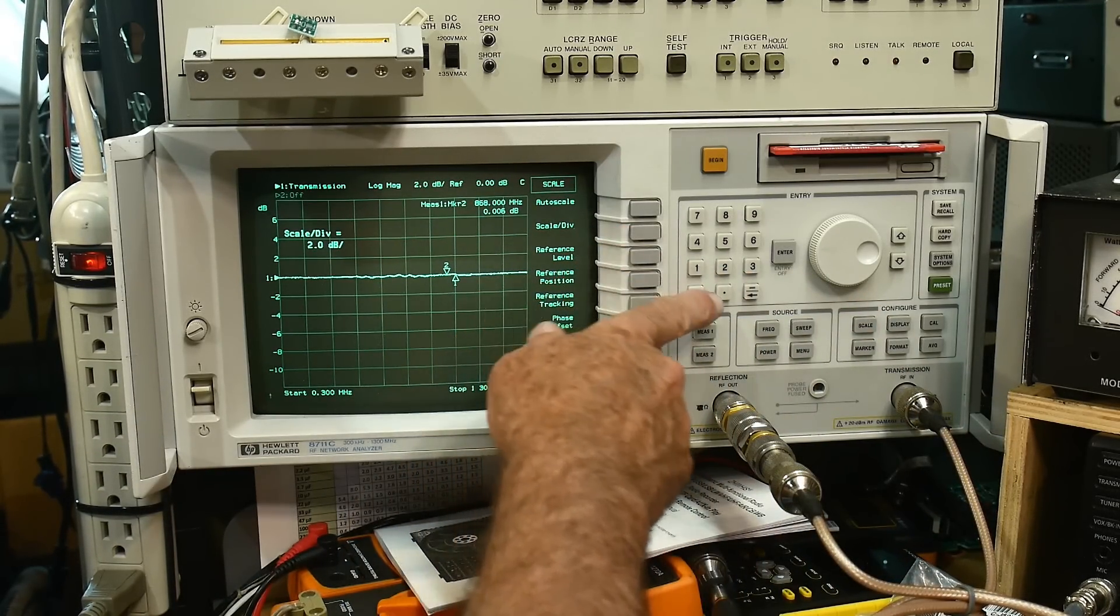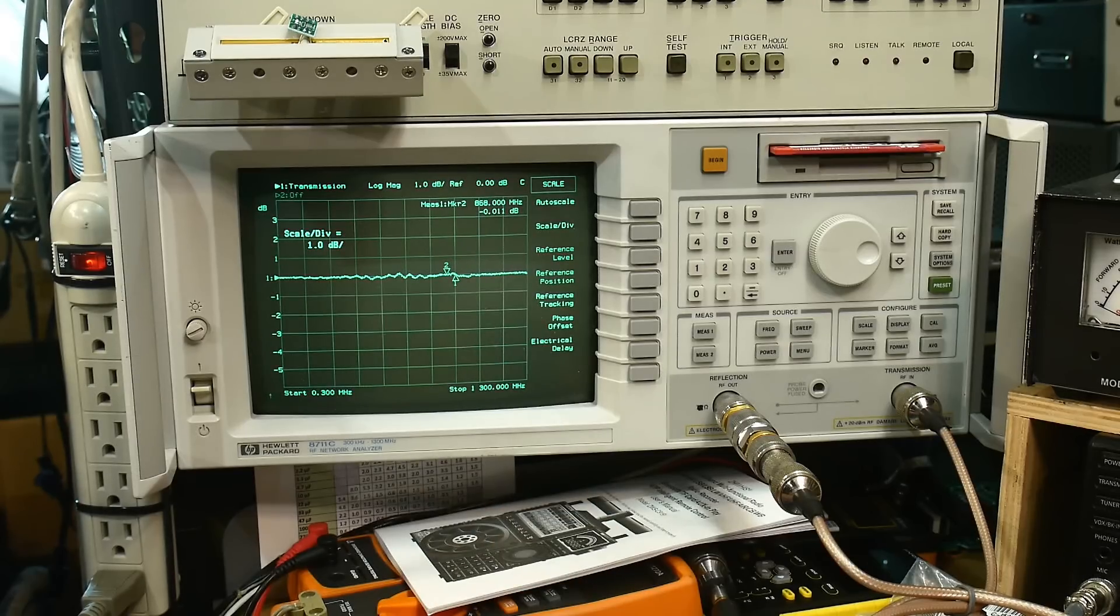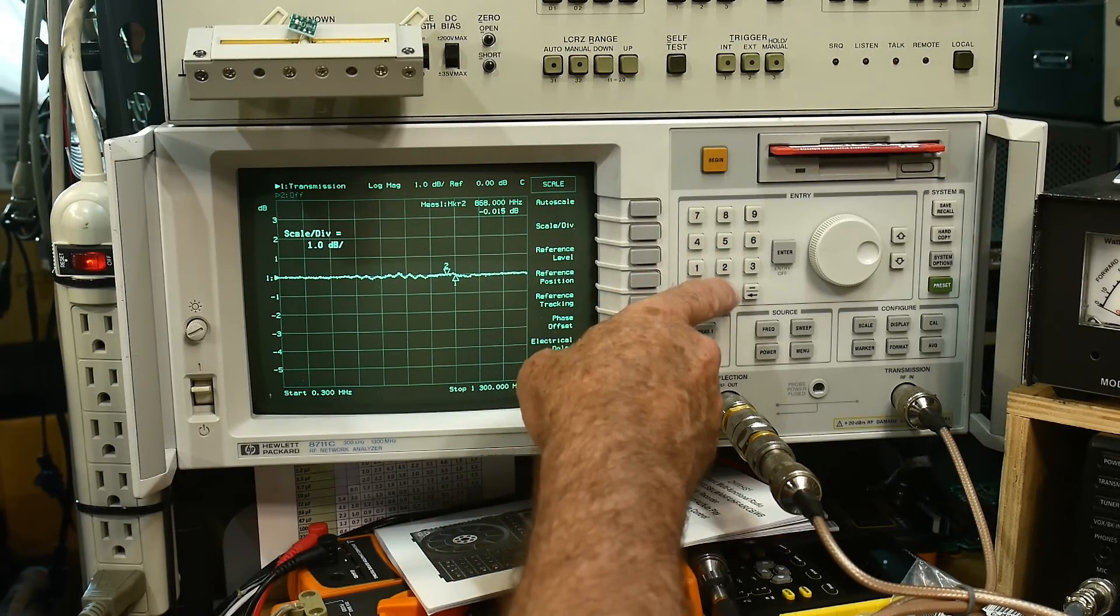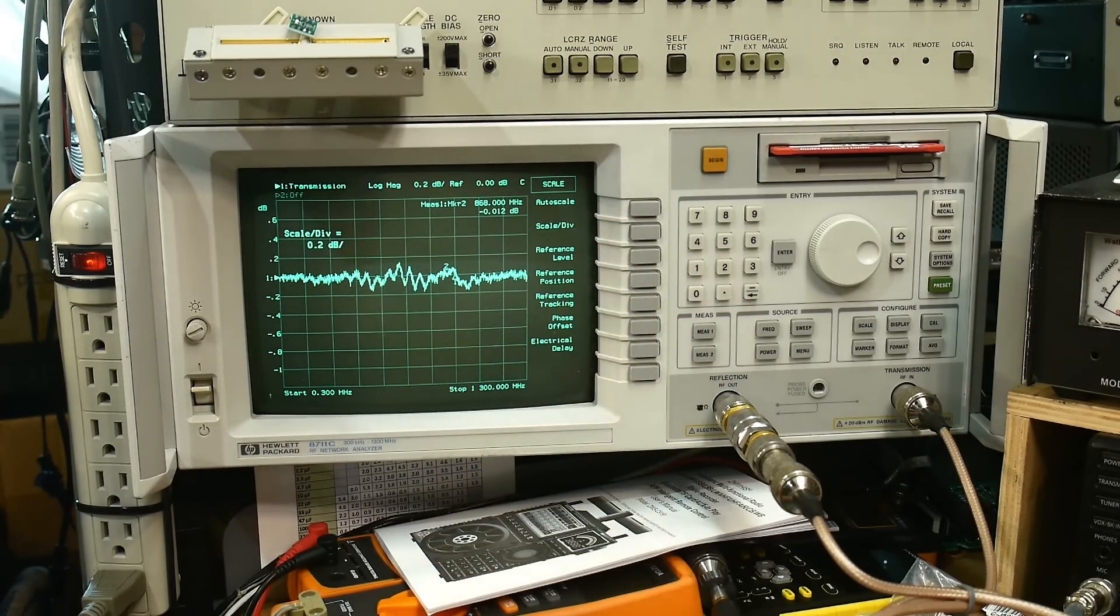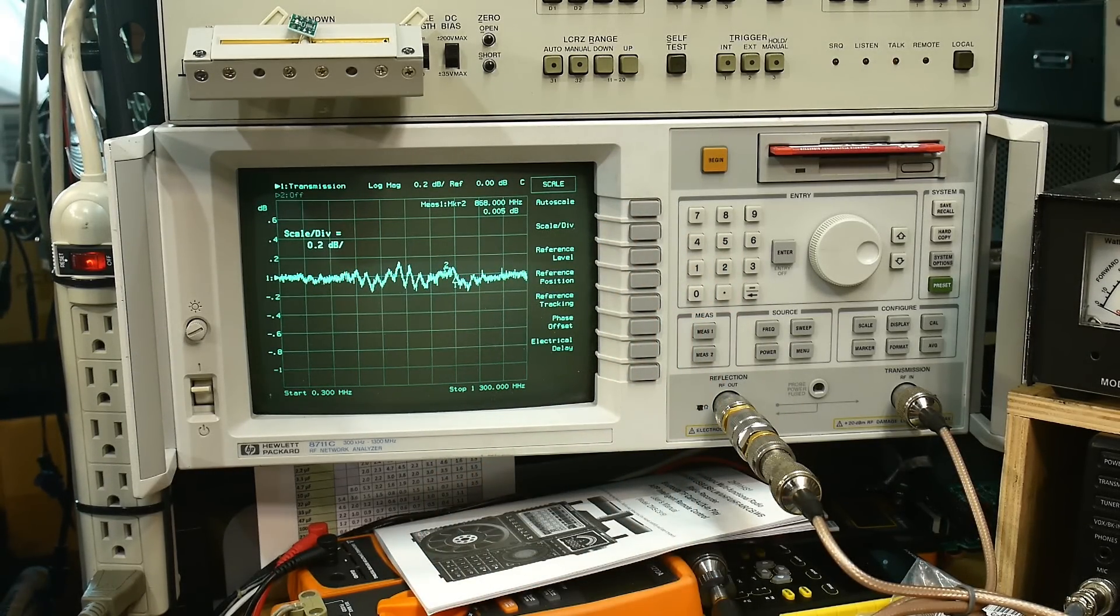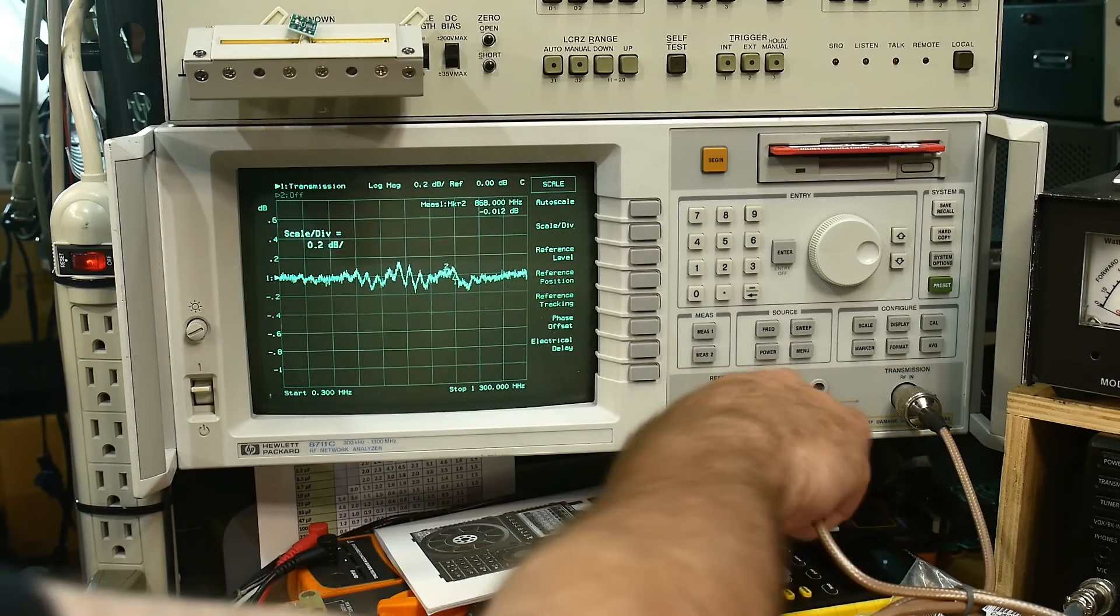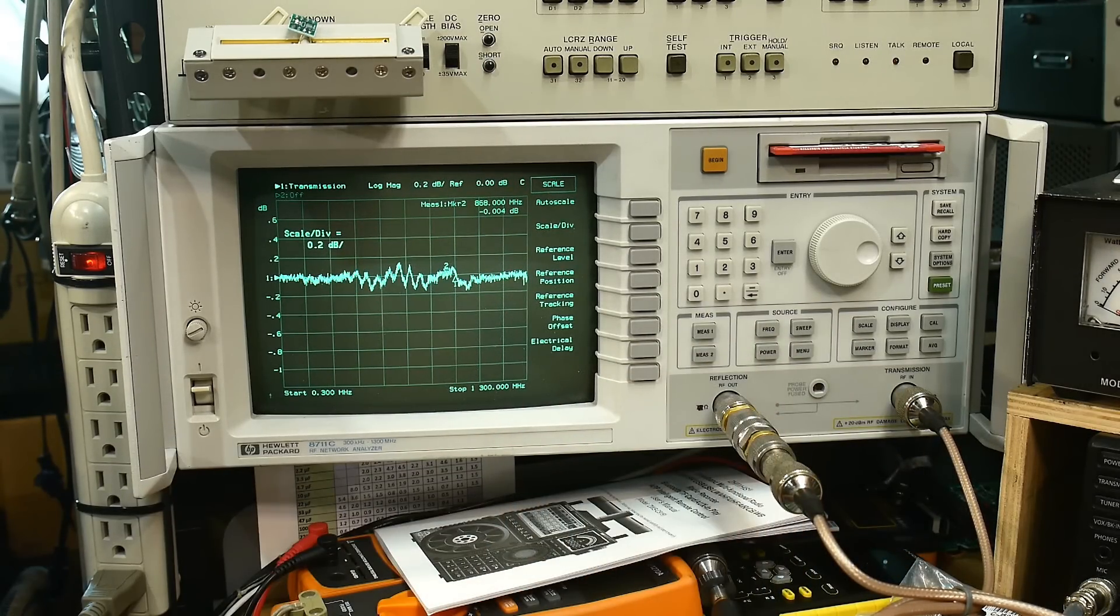And it's looking pretty good. We'll do scale 1dB per division, scale of 0.2dB division. Yeah, so about 0.1dB, little ringy stuff, and you can just imagine that just, who knows what's causing that, but I don't think it's those APC 7s causing it.